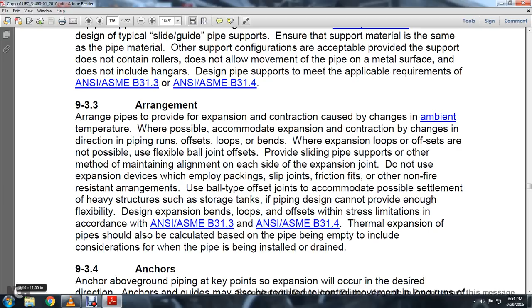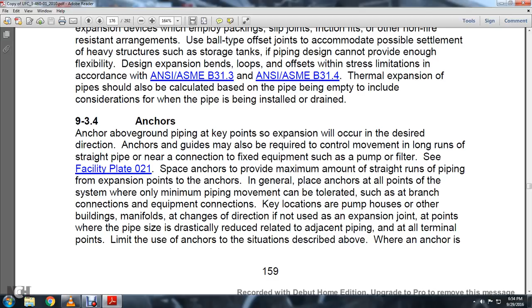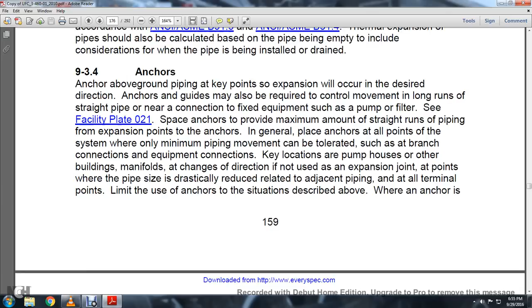Space anchors to provide the maximum amount of straight runs for the piping expansion points. In general, place the anchors at all points of the system where only minimum piping movement can be tolerated, such as a branch connection and equipment connection. Key locations are the pump house or other building manifolds, to change the direction, and anchors are not used for the expansion joints at points where the pipe size drastically reduces relative to the adjacent piping. At all terminal points, limit the use of anchors in situations described above. When an anchor is welded directly to the pipe, ensure the anchor material is compatible with the pipe material.